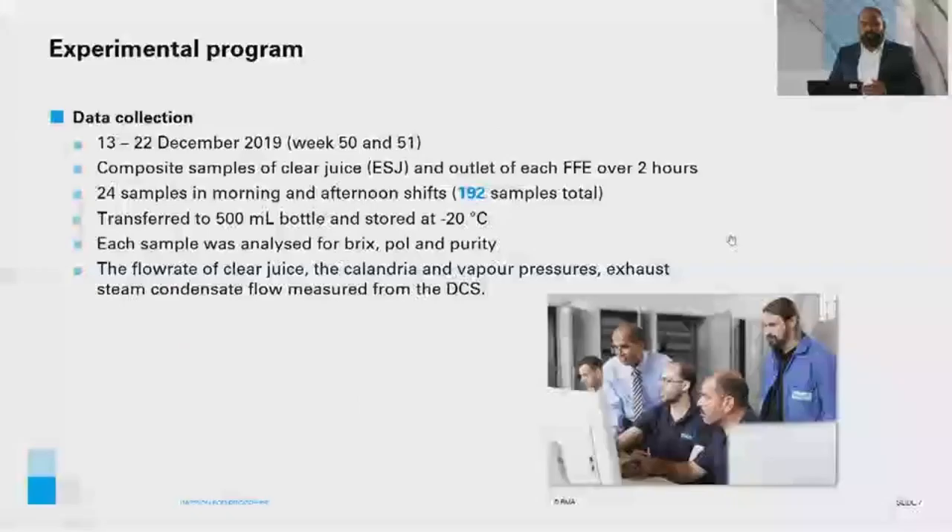The experimental program was undertaken from 13 to 22 December 2019. Composite samples of clear juice — sometimes referred to as evaporator supply juice — and outlet of each falling film evaporator were collected over a period of two hours. 24 samples were collected in the morning and afternoon shift, with 192 samples collected over the entire program. Each sample was transferred to a 500 milliliter bottle and stored at minus 20 degrees Celsius. The sample was analyzed for brix, pol, and purity. The flow rate of clear juice, the calandria and vapour pressures, and the exhaust steam condensate flow were measured from the DCS.